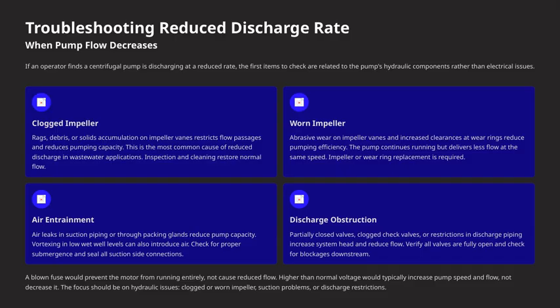One common cause is a clogged impeller. Debris, rags, or solids can accumulate on the impeller vanes, restricting the flow passages and reducing the pump's capacity, especially in wastewater applications. The good news is that inspection and cleaning usually restore normal flow quickly. Another typical issue is a worn impeller.